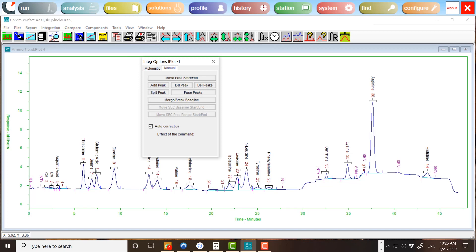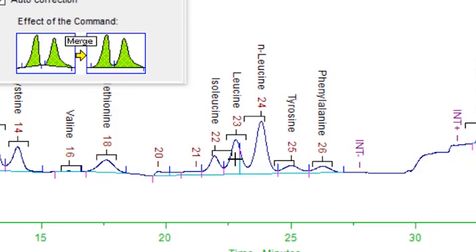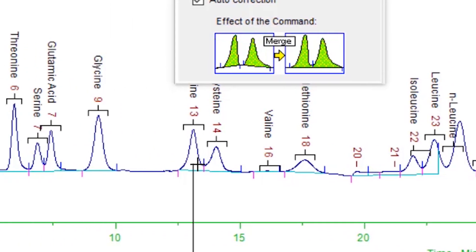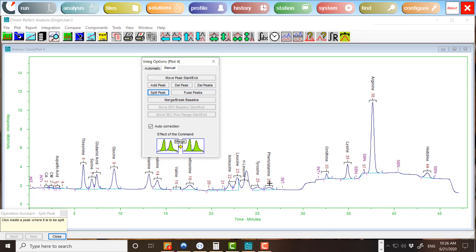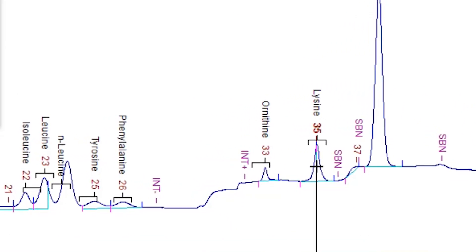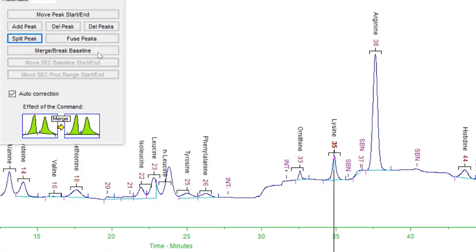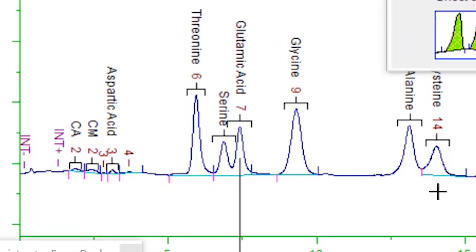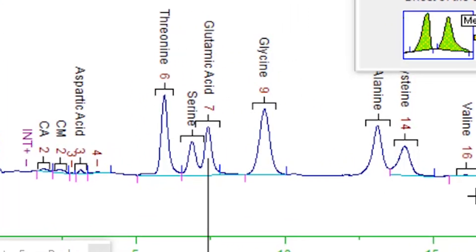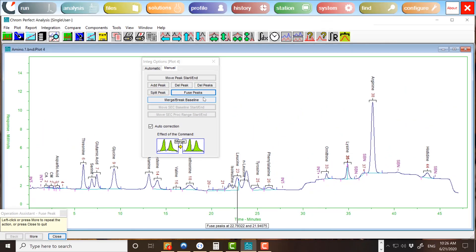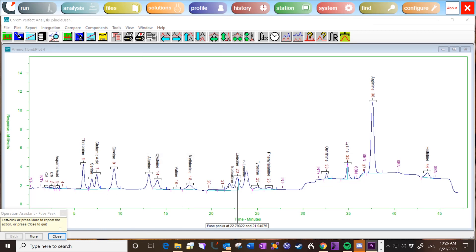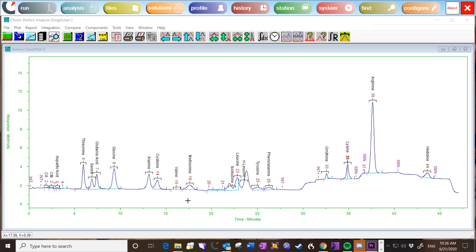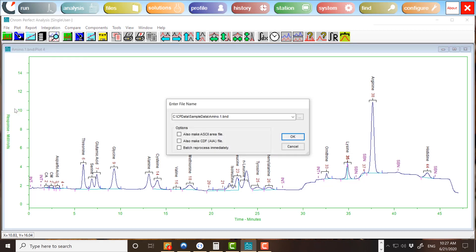This process of left-click to select and right-click to confirm is used to delete a peak, to split a peak, to fuse adjacent peaks, to merge or break the baseline. When you master the left-click and right-click combination, you will be able to quickly make changes to your chromatograms. Remember, only automatic timed events can be saved to the method, which is why this approach is preferable to manual integration. When you have completed the operation, remember to bind your file to save the changes.